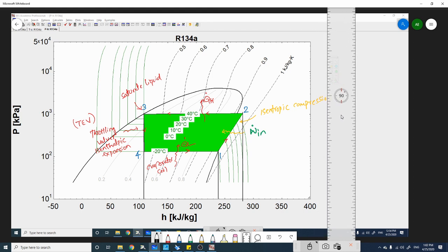So now if you look at the set of values that you have arrived at, you will realize the importance of drawing vapor compression cycles on pressure enthalpy charts. On the x-axis, if you look very carefully, the specific enthalpy is starting with a value of minus 50. Please bear in mind that these are not the absolute values. These are zeroed at a particular reference state, so you may likely get a minus value. That doesn't mean the absolute value is minus 50. So please keep this in mind.